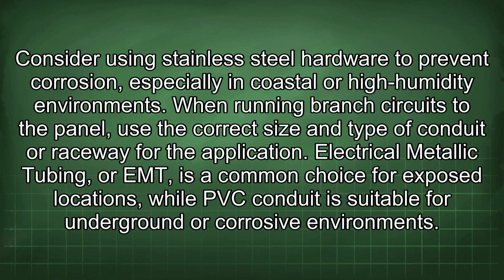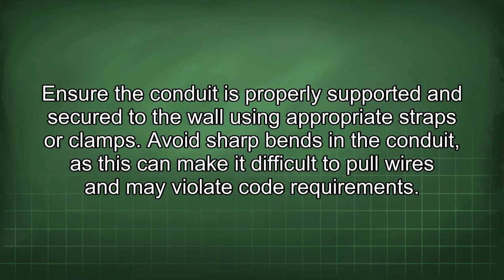When running branch circuits to the panel, use the correct size and type of conduit or raceway for the application. Electrical metallic tubing, or EMT, is a common choice for exposed locations, while PVC conduit is suitable for underground or corrosive environments. Ensure the conduit is properly supported and secured to the wall using appropriate straps or clamps. Avoid sharp bends in the conduit, as this can make it difficult to pull wires and may violate code requirements.